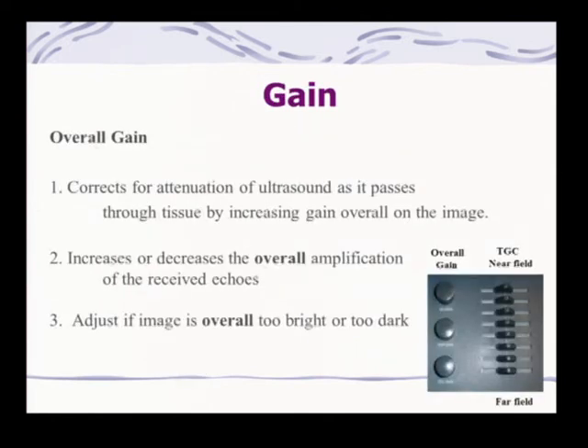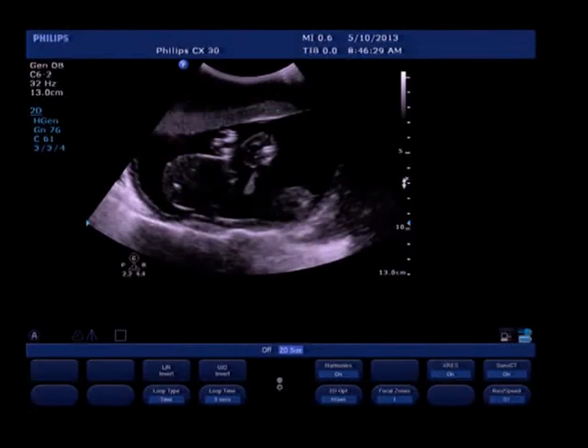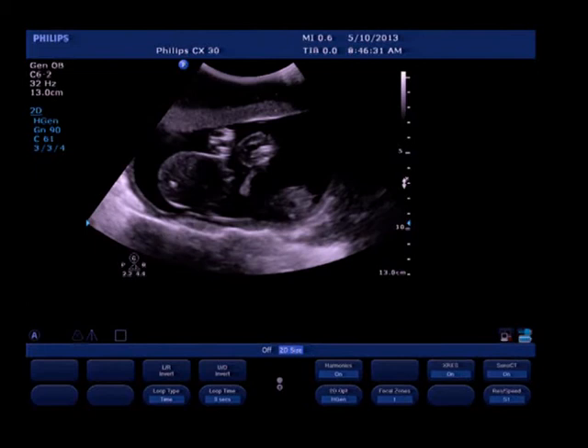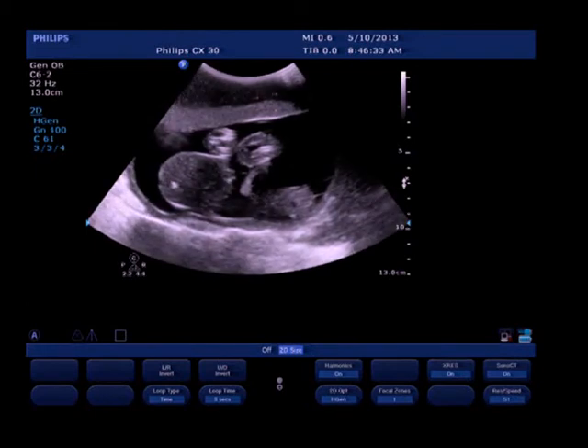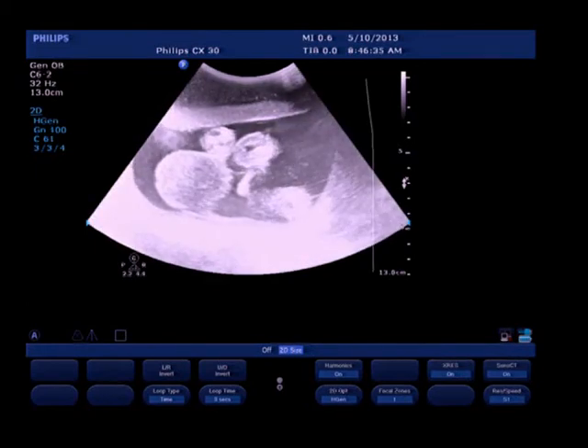Now next is the gain control. That corrects for the attenuation of the ultrasound as it passes through the tissue, and that can be an overall gain or a gain in a particular spot. So what I'm going to do here, this can make your image either too dark or too bright. And I'll just flick back. And Tracy's going to turn the gain right up now, the overall gain. And you can see what happens. It's unreadable, really.